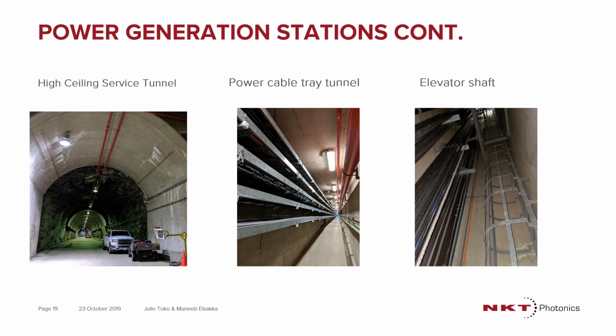Same thing with elevator shafts, where these are areas where it's really hard to set up a different form of fire detection system like smoke detectors. One advantage is definitely to use linear detection, but for really long shafts, it's important to have a distributed fiber optic linear detection.